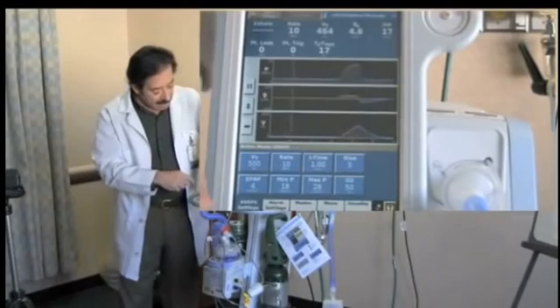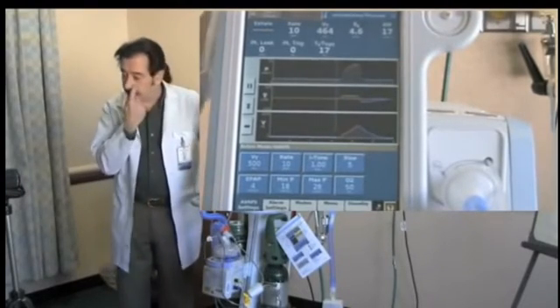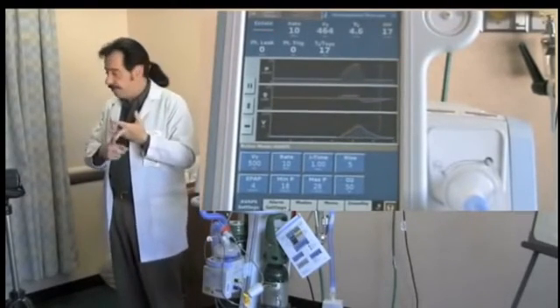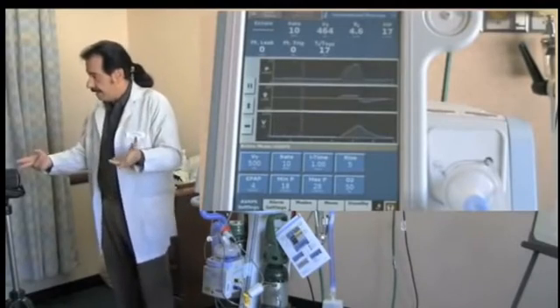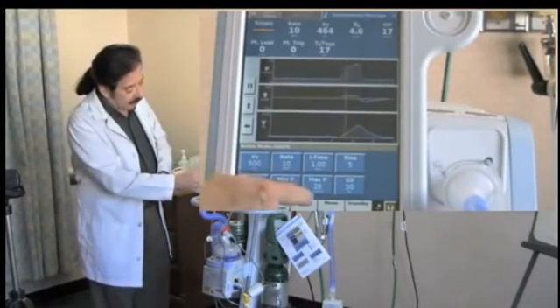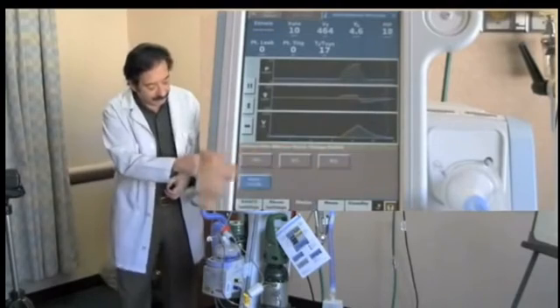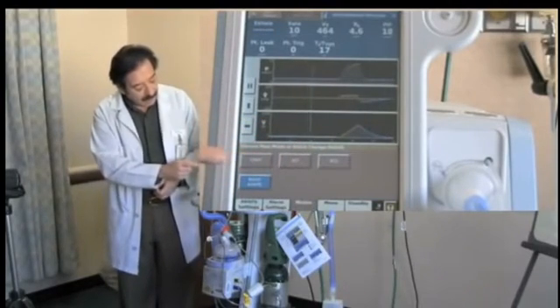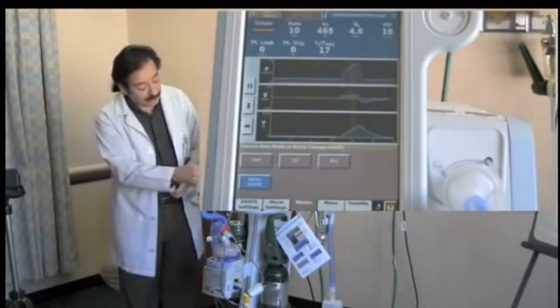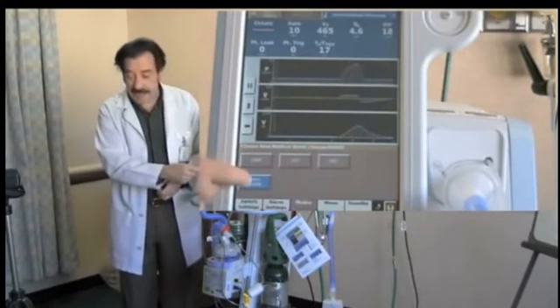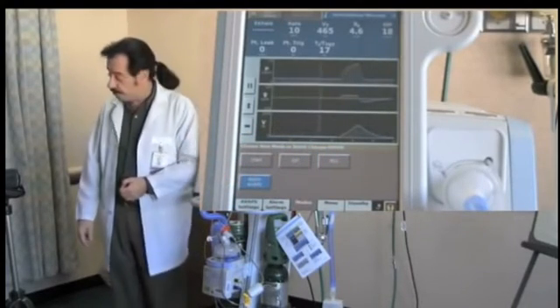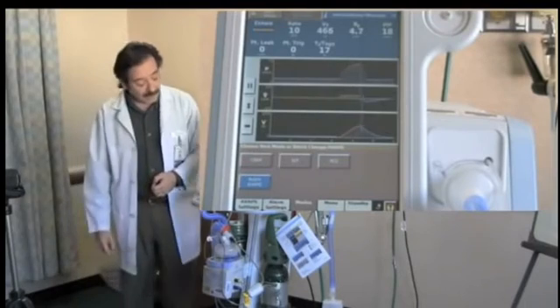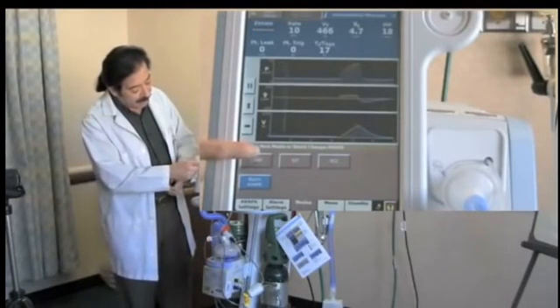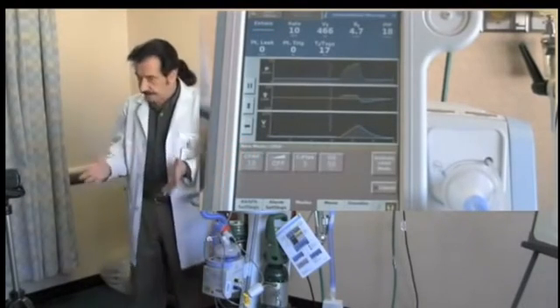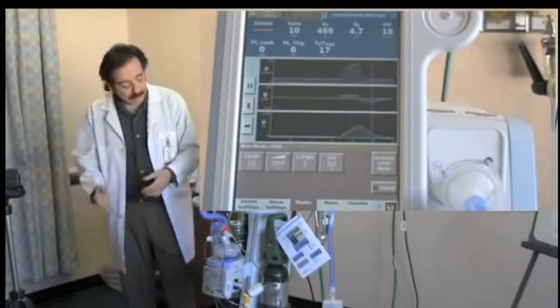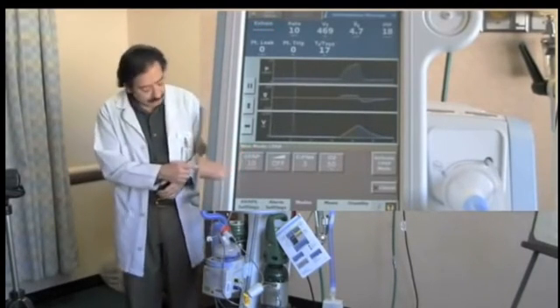Okay. All right, let's talk about the modes that are available. Now, on the STD and the Vision, you had two modes, CPAP and ST mode. Okay, and those modes are certainly available on this ventilator. Okay, with two new modes added, which is pressure control ventilation and AVAPS, or average volume assured pressure support. We'll talk about each one of those individually. In the CPAP mode, there's very few settings to have to make. It's a simple mode. Okay, so you have your CPAP level.